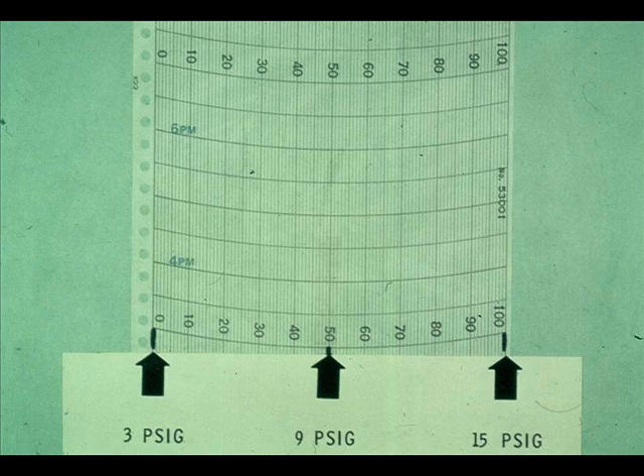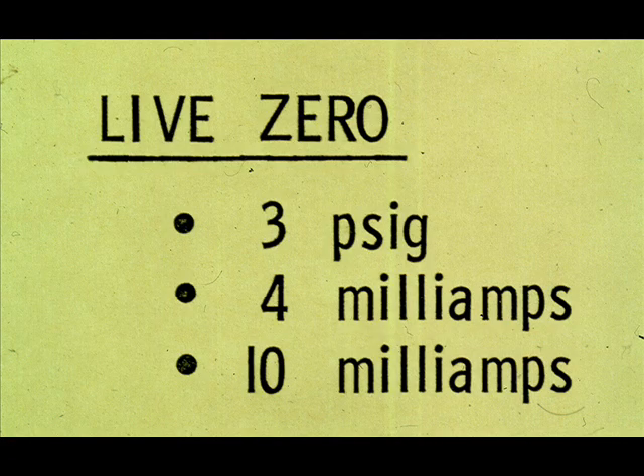This recorder chart is an example of how an air signal from a pressure transmitter positions the process pen. A 3 PSIG signal causes the process pen to read zero. 9 PSIG moves the process pen to mid-scale, and 15 PSIG would move the process pen to the maximum process pressure reading. Notice that the air signal is 3 PSIG when the process pressure is zero. This air signal of 3 PSIG is called a live zero. Similarly, the live zero for electronic instruments is 4 milliamps or 10 milliamps, depending upon the range of signal being used. A live zero is used to prevent a signal failure, which would read zero, from being confused with a minimum process variable reading.